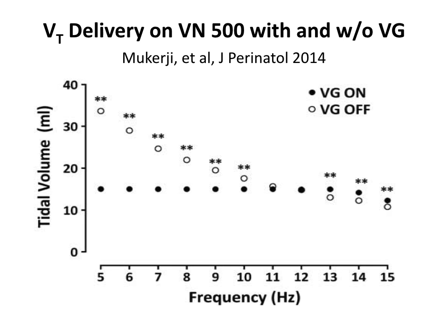And then the expiratory, the negative deflection, which is equal in magnitude to the positive pressure. It is a true oscillator by any measure, because as David explained, it's the waveform that matters. That's generated by a powerful venturi on the expiratory limb. But the limitation here is related to the maximum flow that is available when you open up the solenoids, and obviously the inspiratory time.